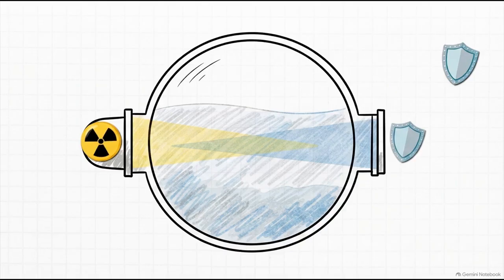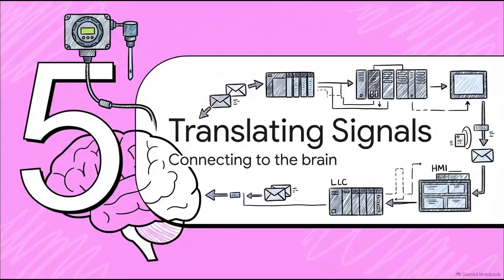You take a heavily shielded radiation source and mount it on the outside of the tank. Then you place a detector on the exact opposite side. The radiation passes entirely through the solid steel walls of the vessel. Based on the attenuation principle, which is just a fancy way of saying how much radiation is blocked or absorbed by the material inside, that detector calculates exactly how full the tank is. You get to measure extreme, harsh process conditions without ever making physical contact. Pretty wild, right?